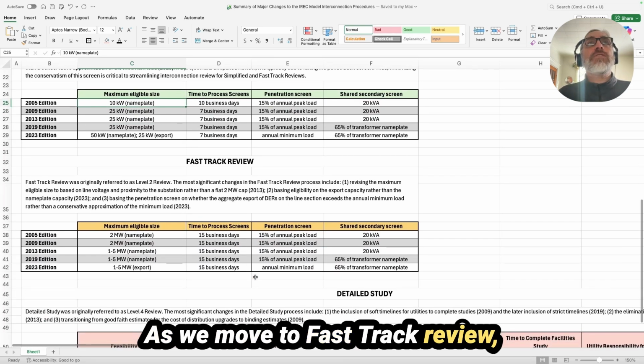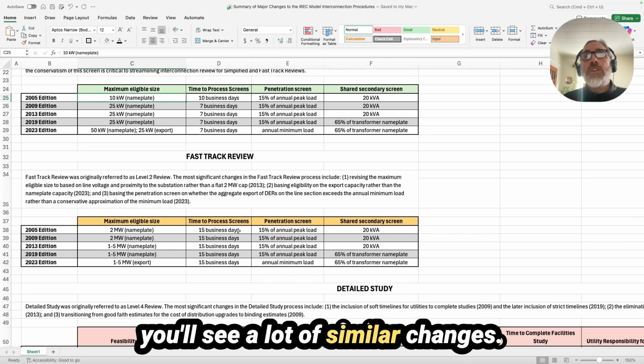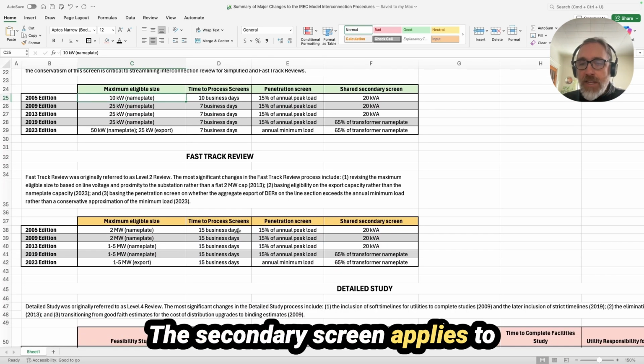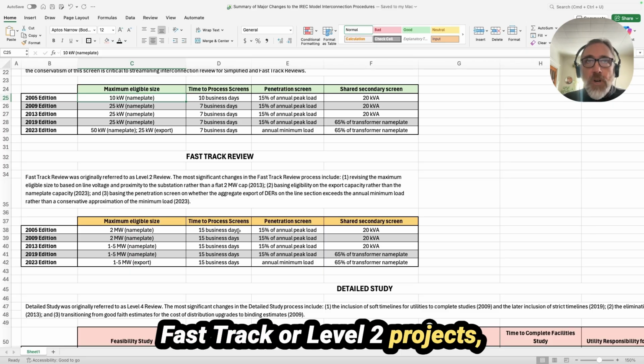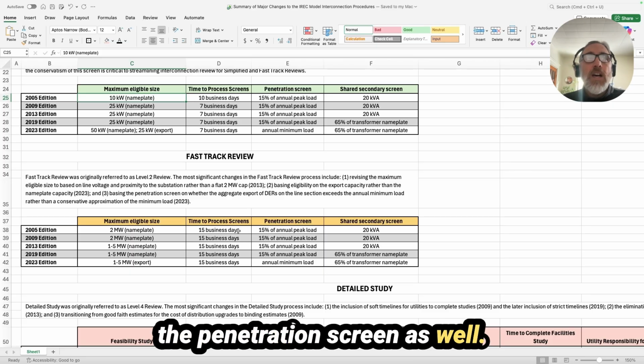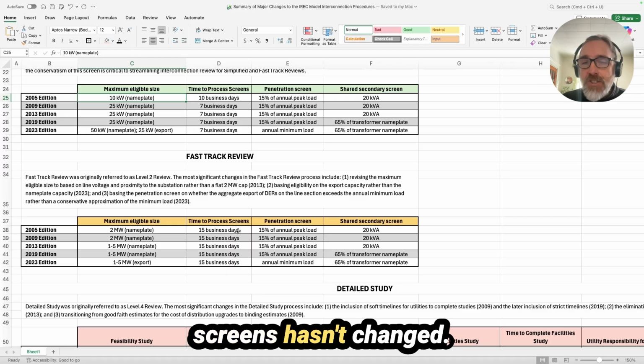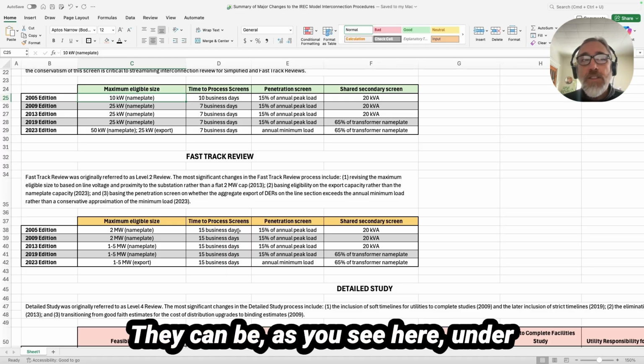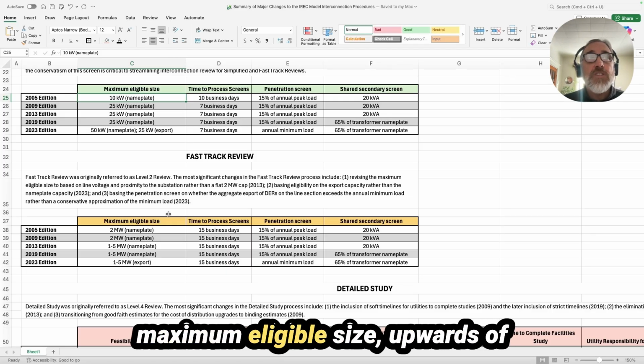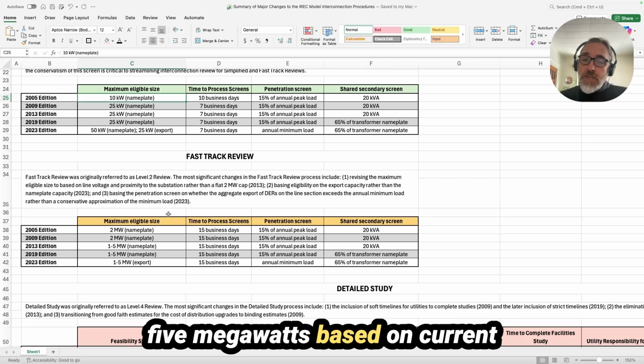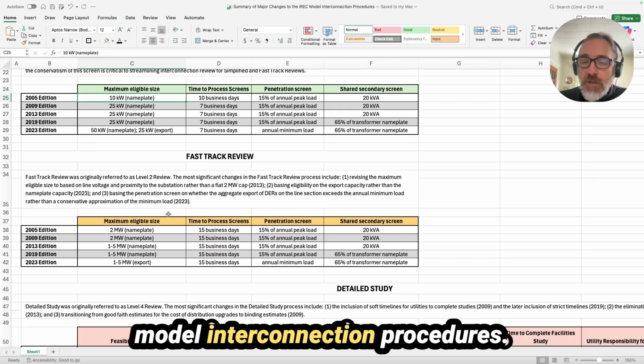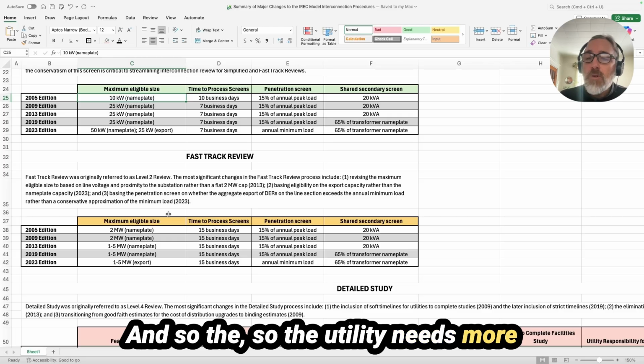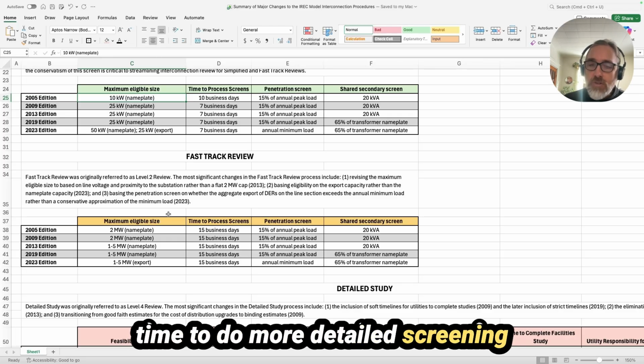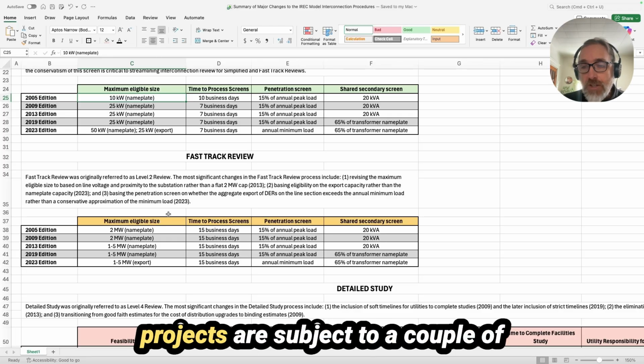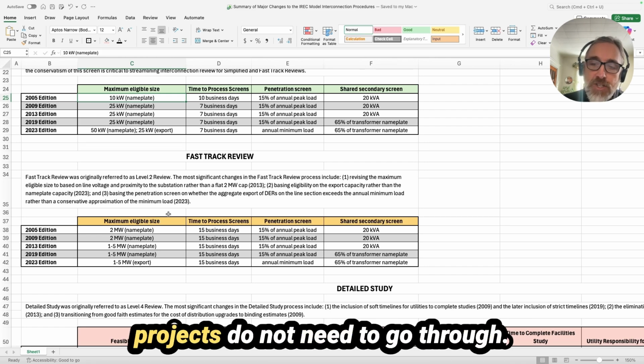As we move to fast track review, you'll see a lot of similar changes. The secondary screen applies to fast track or level 2 projects, the penetration screen as well. The time to process screens hasn't changed. These projects are a bit bigger. They can be, as you see here, under maximum eligible size, upwards of 5 megawatts based on current model interconnection procedures. And so the utility needs more time to do more detailed screening of these projects. And the fast track projects are subject to a couple of additional screens that the simplified projects do not need to go through.